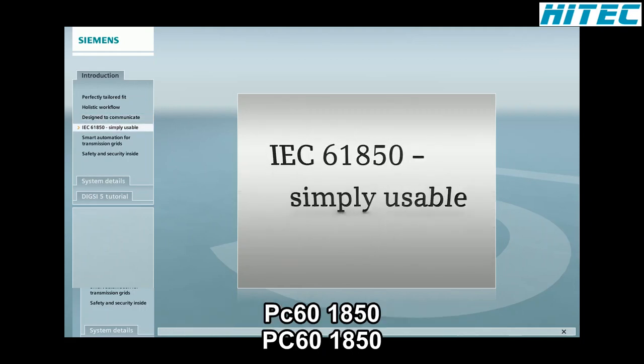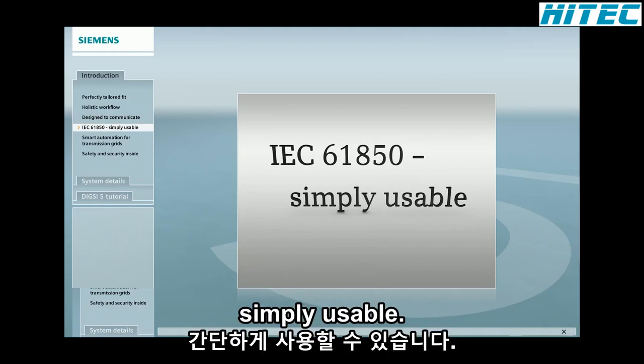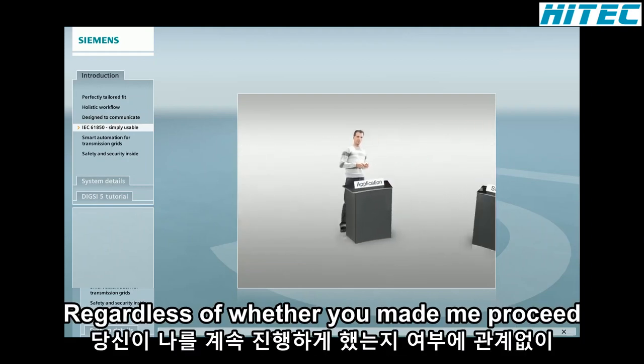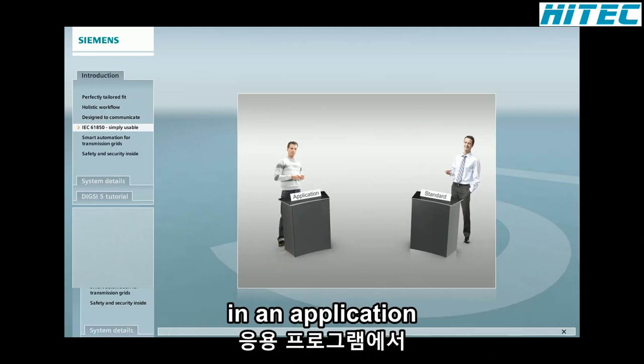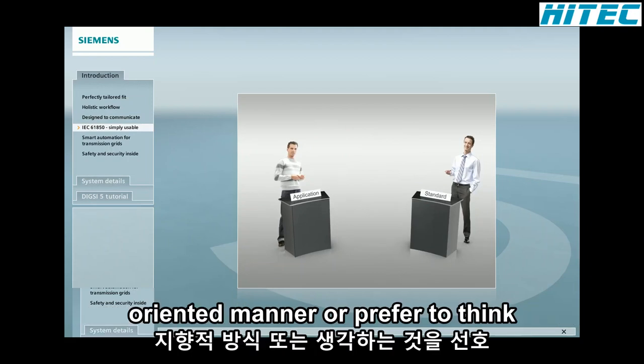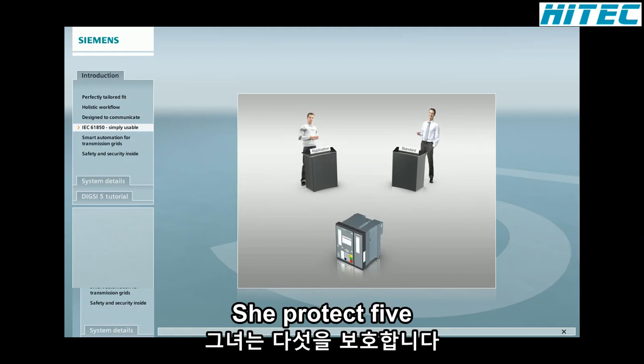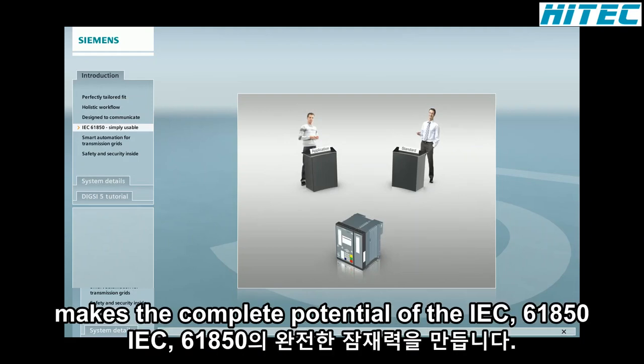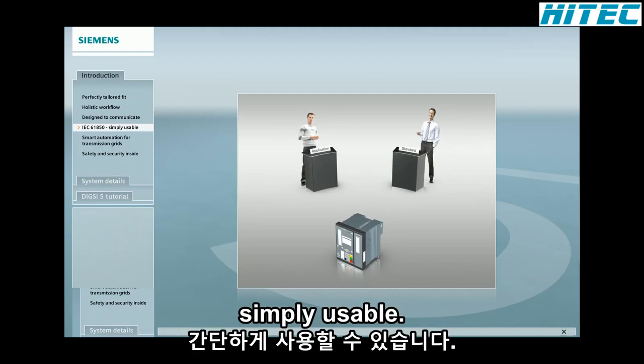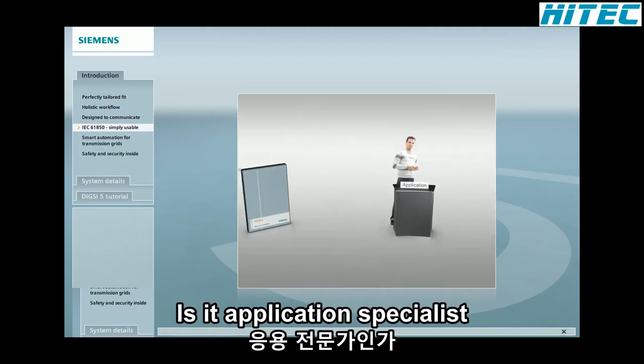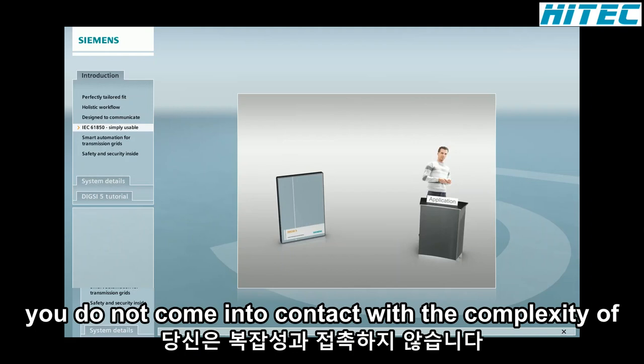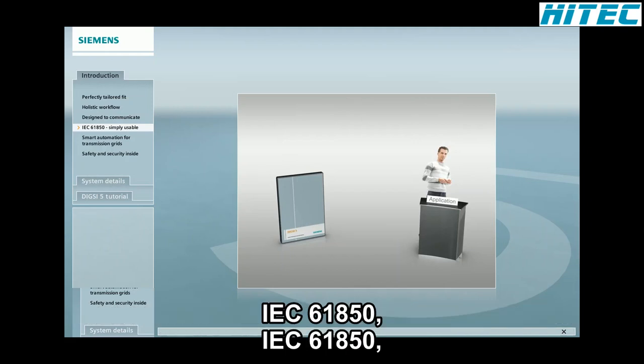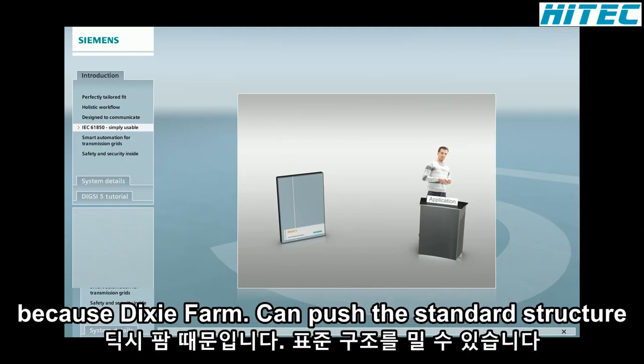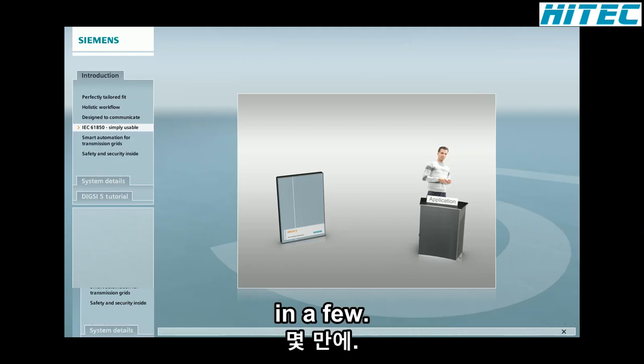IEC 61850, simply usable. Regardless of whether you mainly proceed in an application-oriented manner or prefer to think in standard structures, SIPROTEC 5 makes the complete potential of the IEC 61850 world standard simply usable. As an application specialist, you do not come into contact with the complexity of IEC 61850 because DIGSI 5 converts the standard structure into your familiar view.